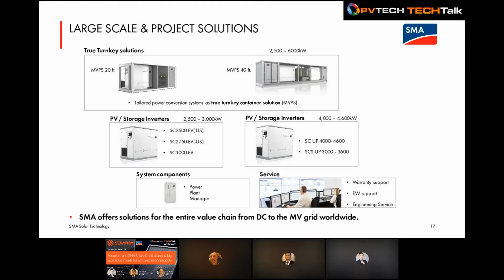So as previously mentioned, when we concentrated on just the PV sector, we have the 20-foot, we'll call this medium voltage power station. That basically means a 20-foot container with the PV inverter, with the medium voltage transformer installed in the middle, and also the switchgear at the back. We have the 40-foot container, which means that we have two central inverters installed, one medium voltage transformer in the middle, and this whole unit can go up to 6 megawatt size.